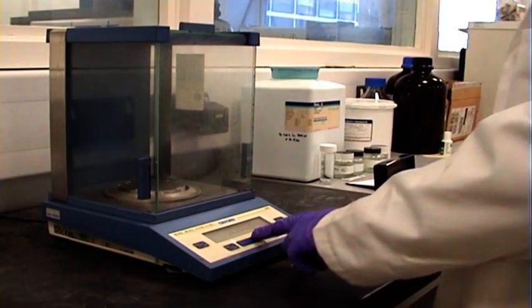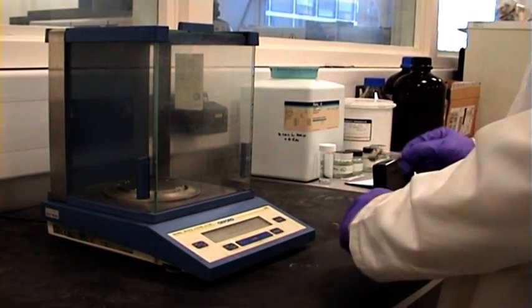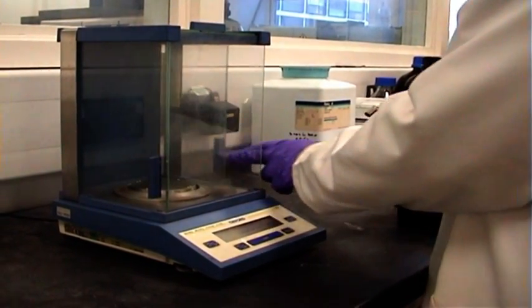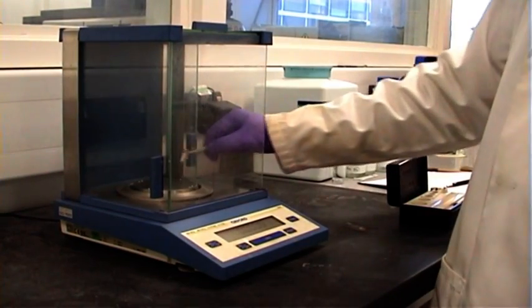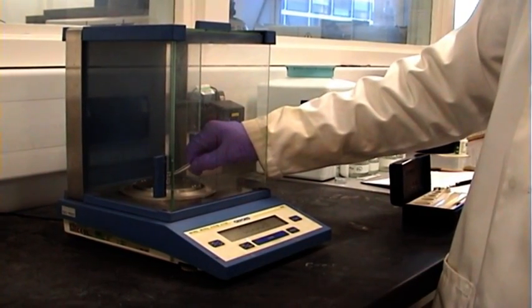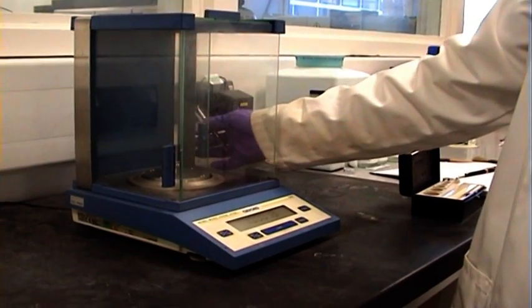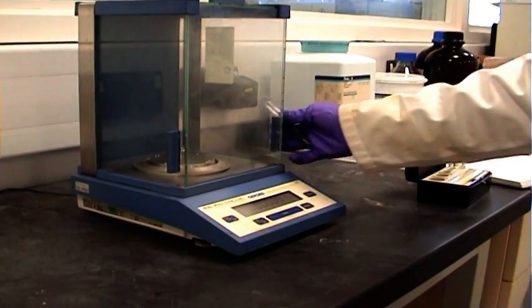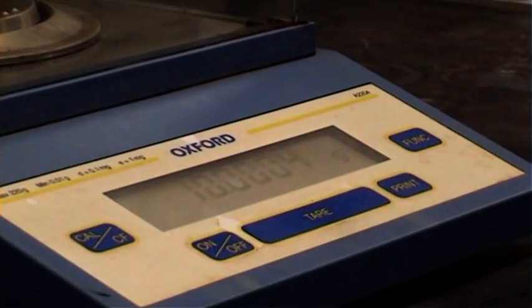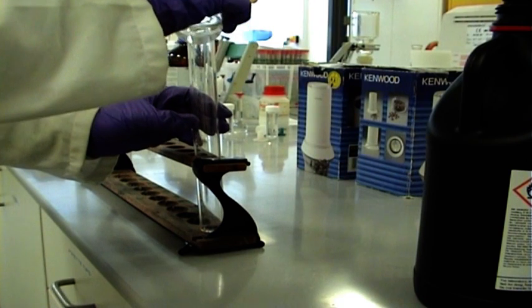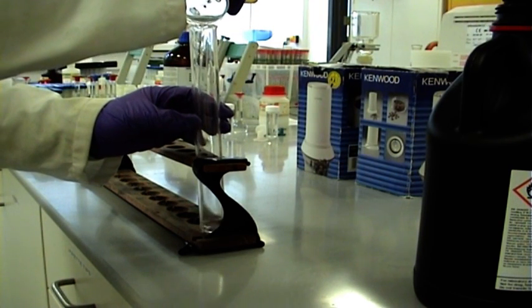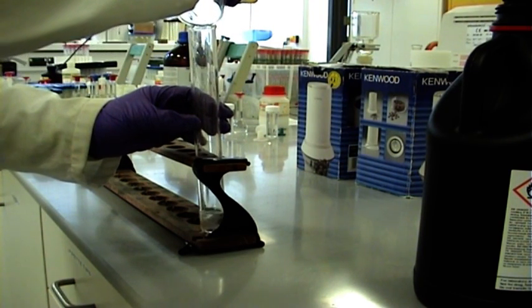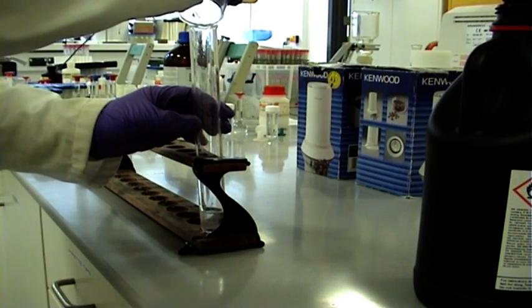As shown in the Part 1 video, we now need to check the calibration of the balance. The analytical balance must be checked that its calibration is correct using certified weights of known mass. Here, a 10-gram weight is being used. While the checking process is being conducted, the digestion step can be started with the digestion vessels being pre-cleaned ready for use. In this case, we'll be using a sulfuric acid-based wet digestion method.